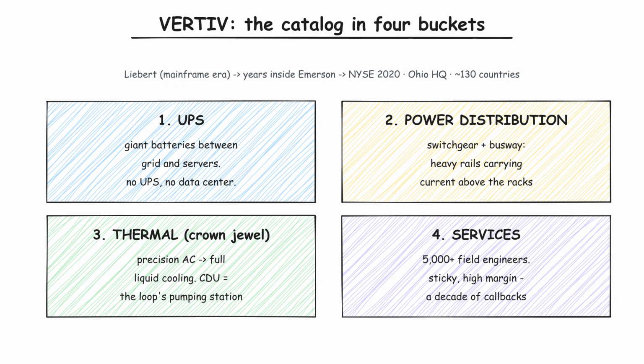Bucket 2, power distribution: industrial grade switchgear and busway, the heavy metal rails that carry current above the racks. Bucket 3, the crown jewel, thermal management: everything from precision air conditioning to complete liquid cooling systems, including the coolant distribution unit, or CDU. The CDU is the pumping station of a liquid loop, feeding coolant to hundreds of chips and handing the heat off to the building's water system. As racks get denser, a CDU stops being optional.